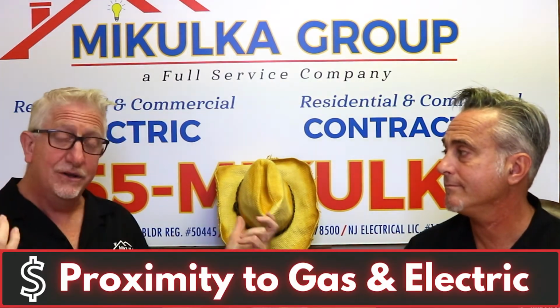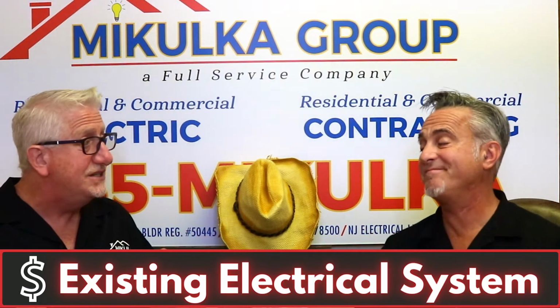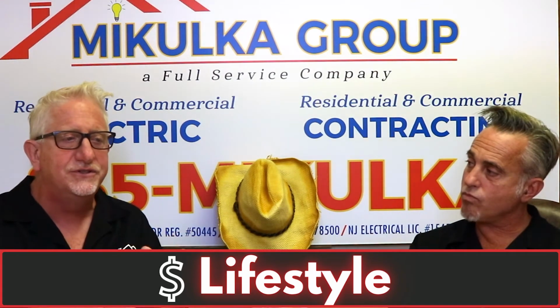The 2 utilities that we need to be close to for a generator are gas and electric. So where your gas meter and your electric meter are definitely drive the cost of where this thing is going to go. Also, the existing electrical system and conditions of your house. If we have to get across your basement and the basement's finished with a sheetrock ceiling, well, guess what? That's tough. If we have to get across the basement, but it's wide open, it's not framed, much easier. So all these things drive the cost. That is why every single house is different, and every single application and family lives a little bit differently than everybody else. So that's something that we have to take into account too. How do you live?